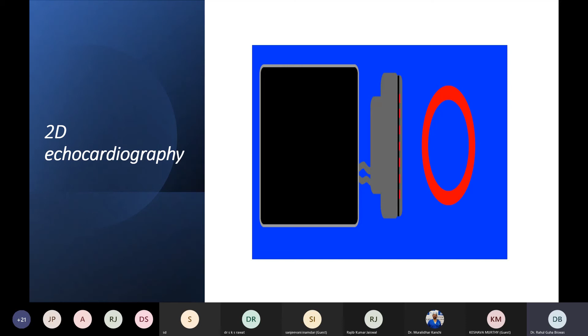Now, M mode is a very brilliant, simple idea. I'm not using all the piezoelectric crystals. I'm only using one, and I'm focusing only on one area. I'm asking the piezoelectric crystal, you keep on firing on that particular area, very quickly get back the image and tell me what it is showing. So because I'm using only one crystal, my pulse repetition is very high and it can adequately trace the movement of a fast moving structure.